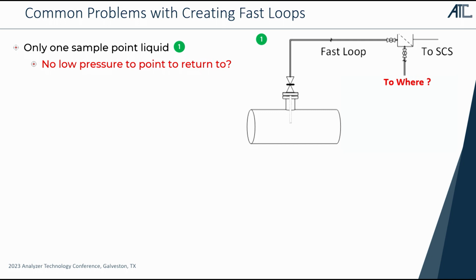And there's a lot of issues and common problems that come up when we start to consider, how am I going to implement a fast loop at my facility? One of the common ones that we'll see is we only have one sample point. So we have a sample point to measure from, but we don't have a low pressure return point. So we have to try to figure out, where is that low pressure return going to go to? If we don't have a low pressure process point, now we've got to go, well, I can't return back to the same pressure, so maybe I'm going to need a pump. If we're going to return to a low pressure place like the flare header, we may be concerned about the volumes that we're going to put there.